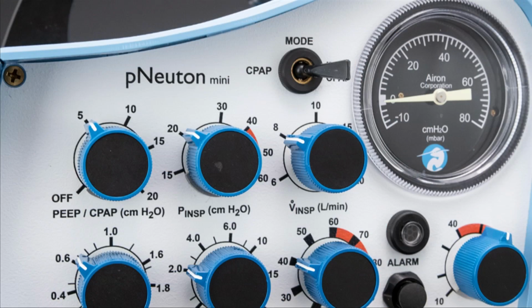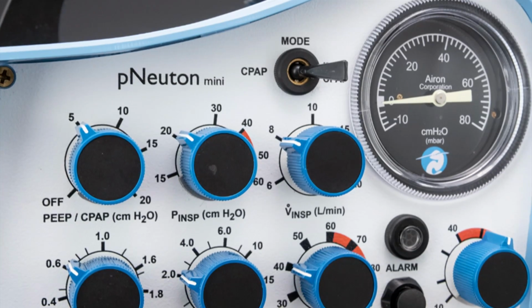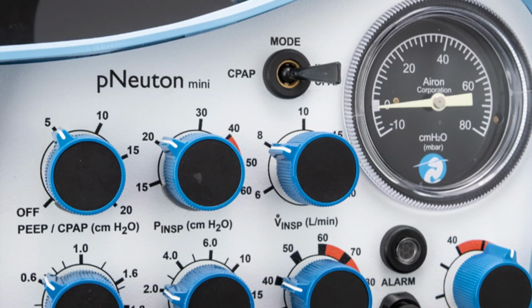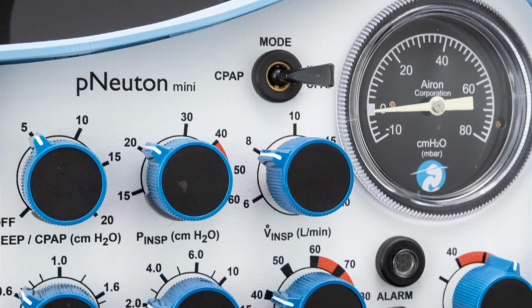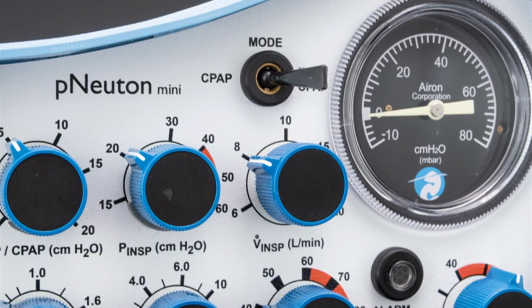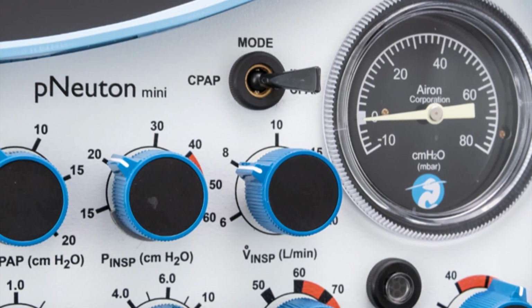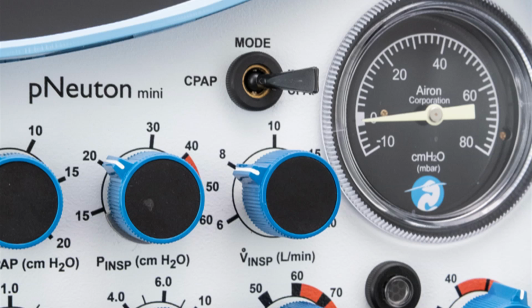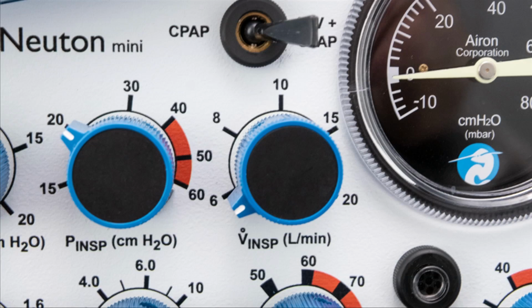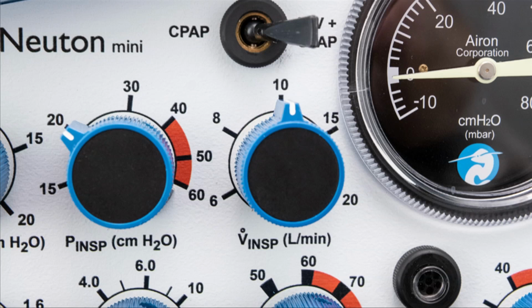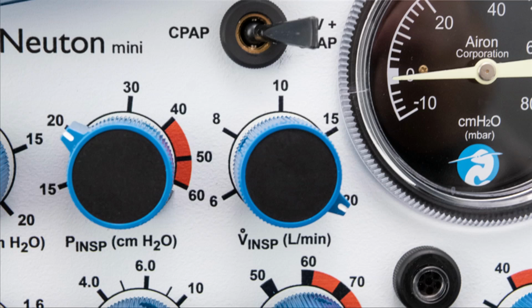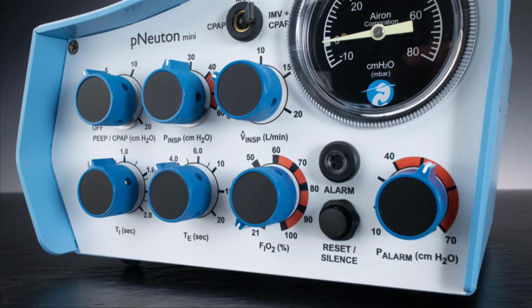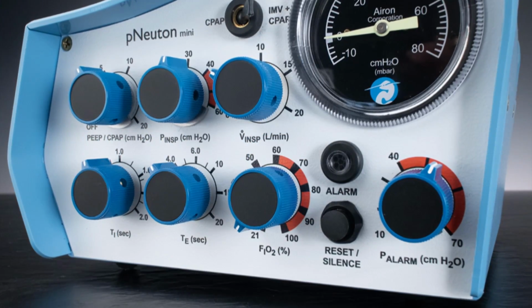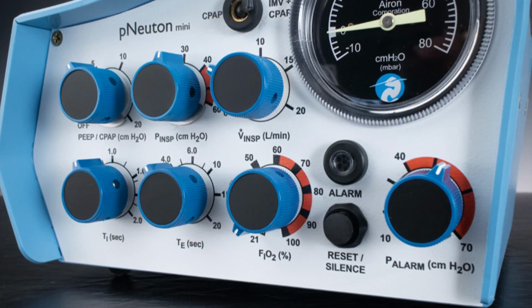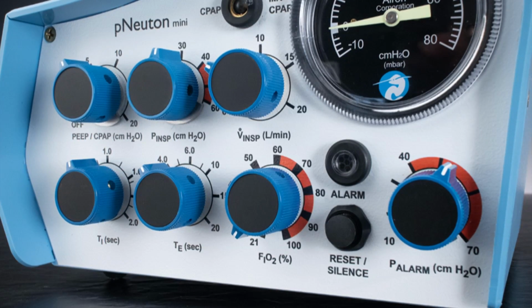Continuous flow control. Moving to the right one more time is the VINSP, or continuous flow control. One of the key advantages of the Mini over many other portable neonatal ventilators is that the Mini offers 5 flow settings. The continuous flow through the patient circuit can be set for 6, 8, 10, 15, and 20 liters per minute, which allows you to support a wide range of patients with varying needs. Continuous flow selection is a dependent factor on patient weight for neonatal, infant, and pediatric. Please always use your institution's protocols.